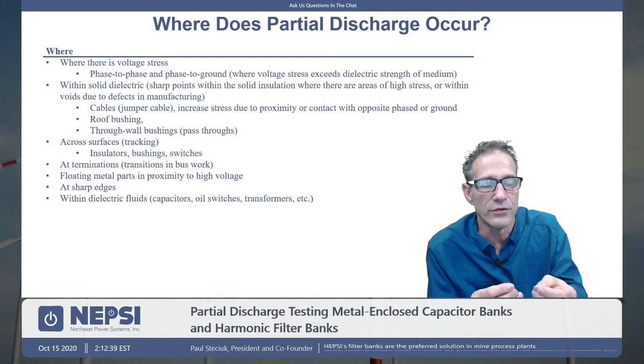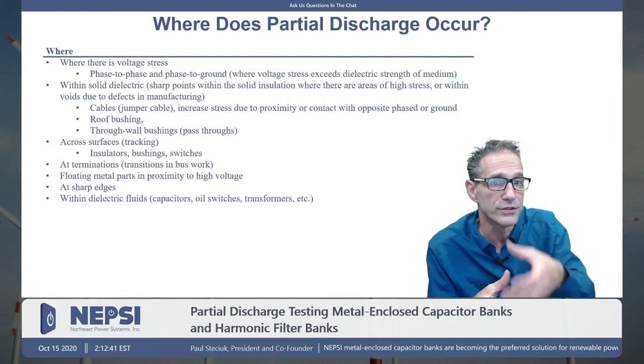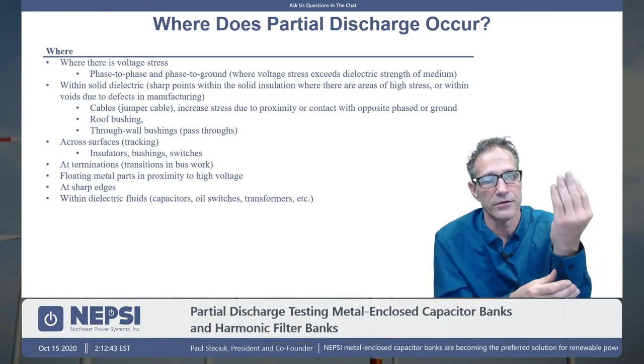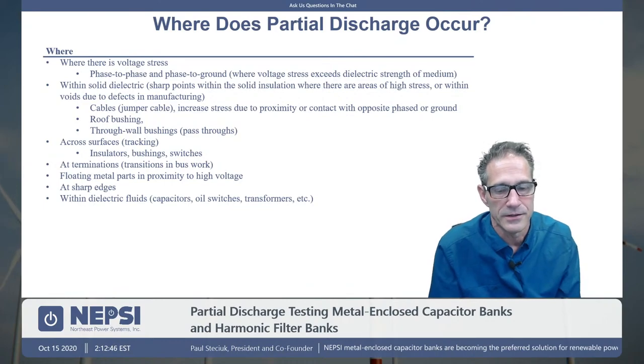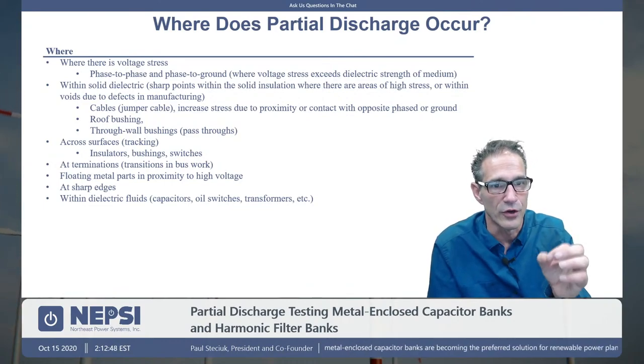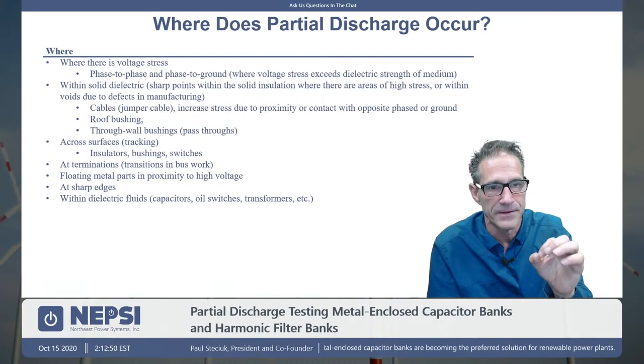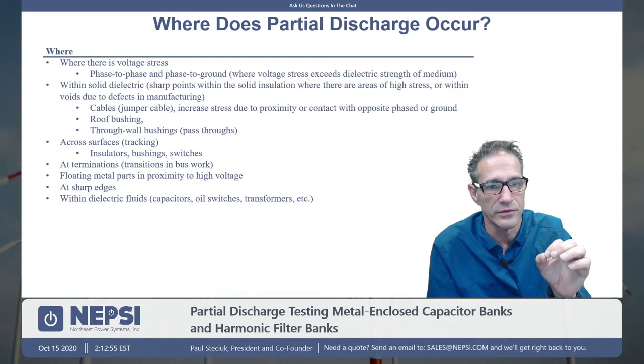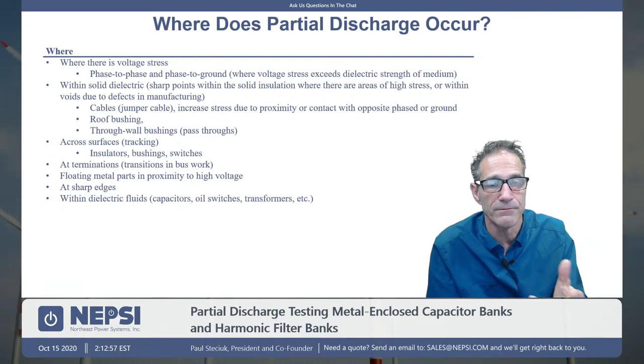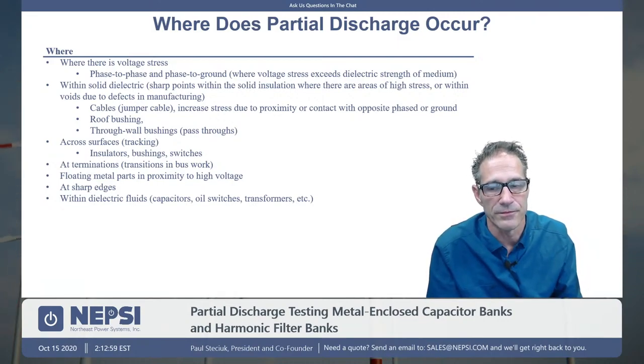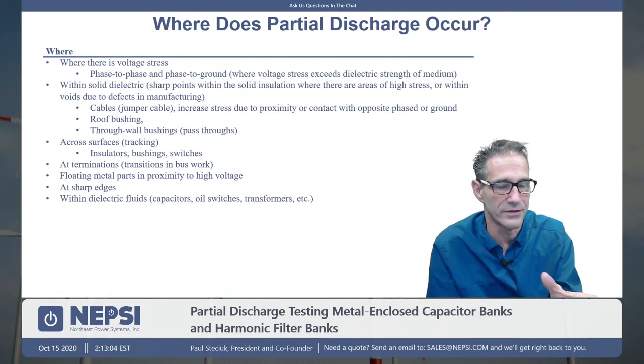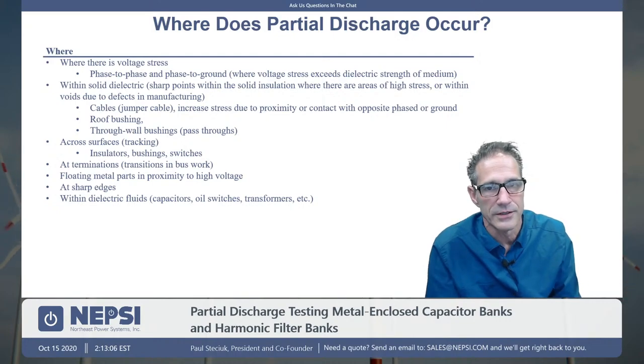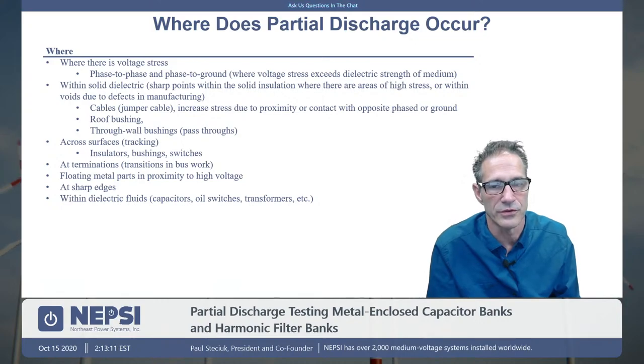You could also have voids within that insulation, say it was a bushing, an epoxy bushing that passes through a roof. If during the manufacturing process there was an air bubble left inside that bushing, you would have partial discharge across the air bubble within that bushing. And eventually that bushing could fail. And this is the point: you would not see that because it's inside the bushing. You would not see a glow or a corona. It would only show up on a test that you have this issue going on.